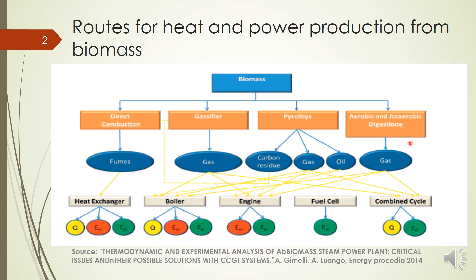Another option is biological conversion — by aerobic or anaerobic digestion we obtain biogas, and that biogas can be used in an engine for power production or in a combined cycle. So these are the different options available for power production using biomass. If we obtain a gaseous fuel from biomass through any method, we can use an IC engine, a fuel cell for direct electricity, or a combined cycle using a gas turbine or steam turbine coupled with a gasifier. Depending on the product and quantity, we can choose one of these routes.